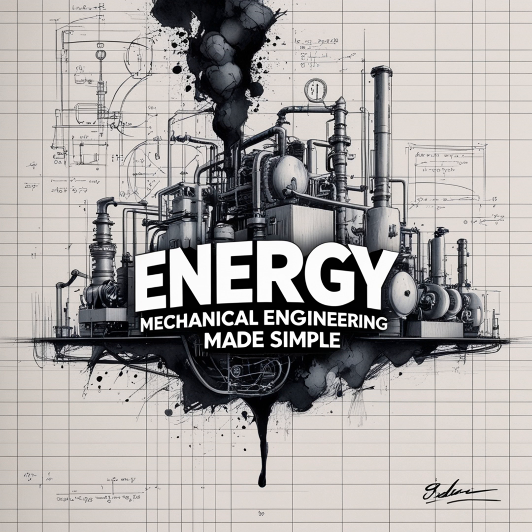Definitely. High N_S machines are good for high flow rates, but low head requirements. Think axial flow fans, like a desk fan or a propeller. They move a lot of air, but don't build up much pressure. And low N_S machines are designed for high head, meaning high pressure, but lower flow rates. These are typically centrifugal pumps or fans with more complex impeller shapes designed to really throw the fluid outwards and build pressure. So calculating the required Q and H, then finding the N_S, guides you to the right type of fan or pump. It's an incredibly powerful selection tool. Gets you in the right ballpark immediately.